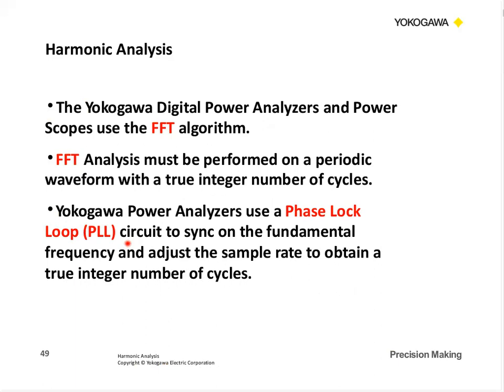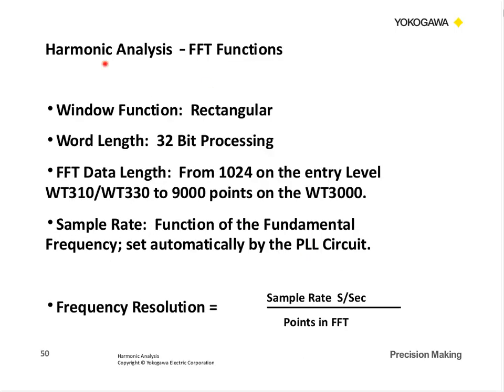It's a digital tuning circuit like you might have on our TVs and radios and things like that. And it syncs on the fundamental, and it adjusts the sample rate internally so that we get a true integer number of cycles to do this FFT calculation on. So that's very important. Some other things on our FFTs: the window function we typically use is rectangular. It's 32-bit processing, and depending on the instrument, the FFT data length can be from 1,024 points on some of our entry-level products up to 9,000 points on some of the high-end products.